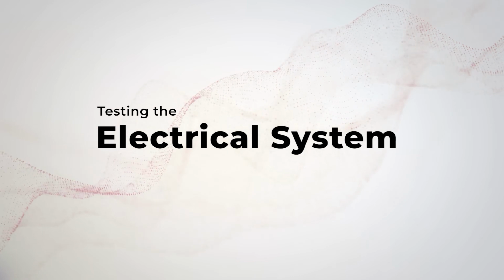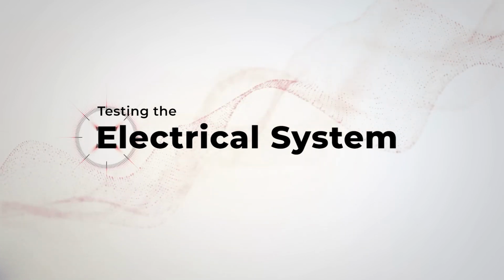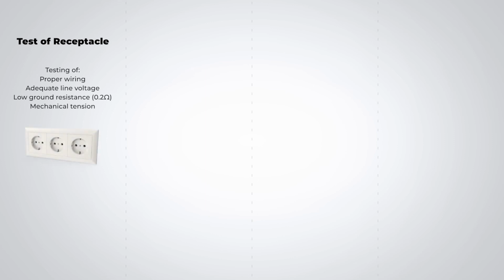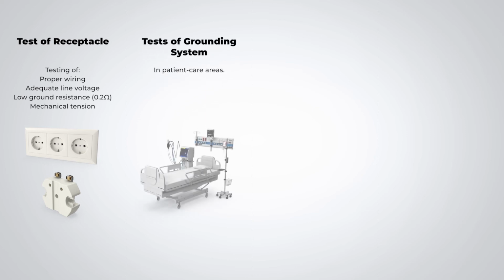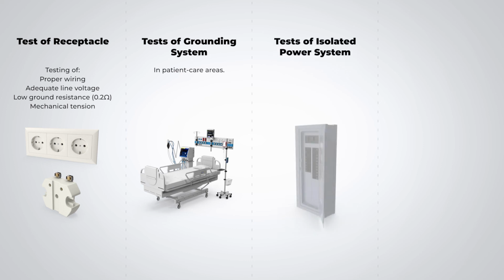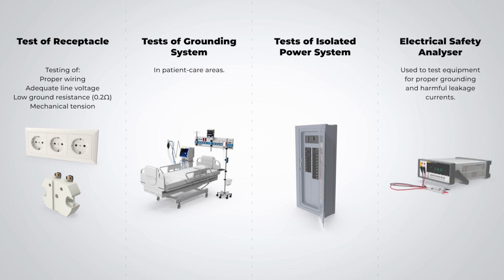Testing the electrical system for faults is a sure way to minimize shock hazards. The following are tests that are commonly performed. Test of receptacle where proper wiring, adequate line voltage, low ground resistance of 0.2 ohms, and mechanical tension are tested. Tests of the grounding system in patient care areas. Tests of isolated power system. And use of an electrical safety analyzer to test the equipment for proper grounding and harmful leakage currents.